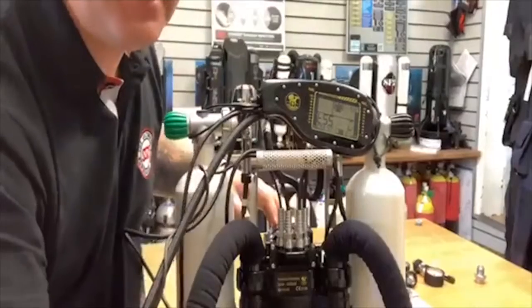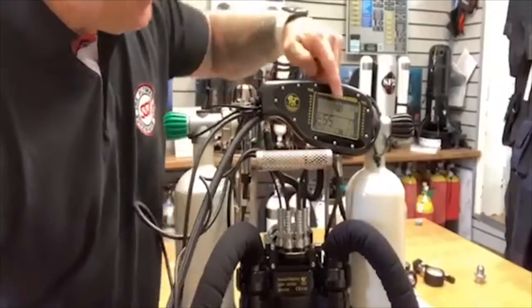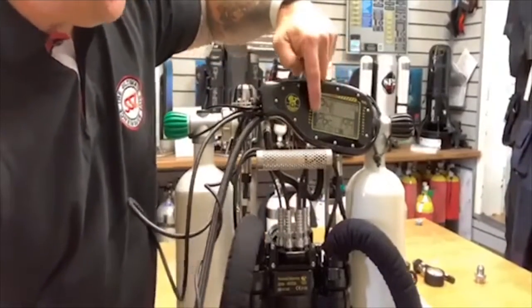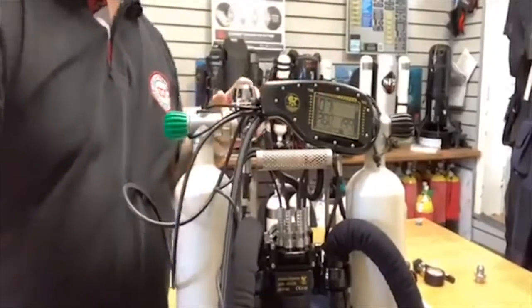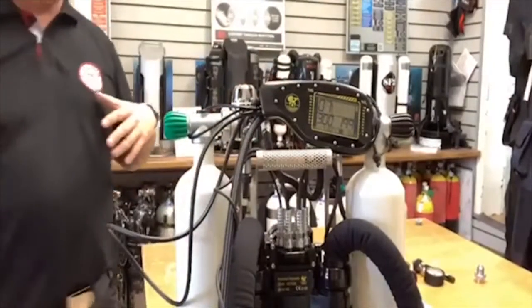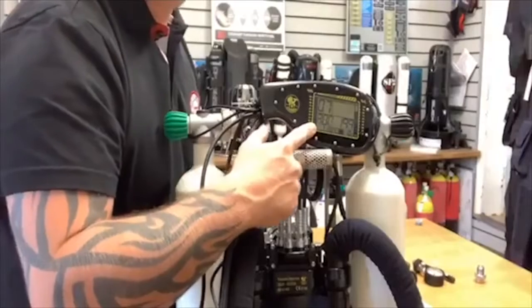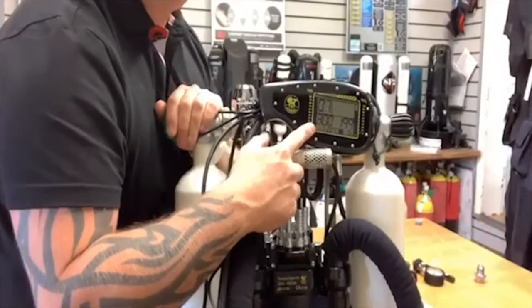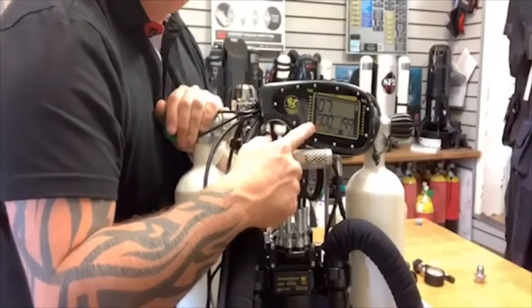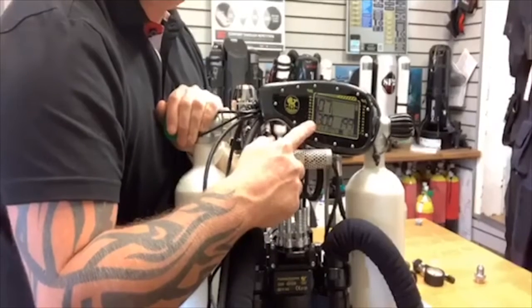that that's working. Test 55 tells me my weeks to service, and test 55 said 105 weeks. So it's got 105 weeks until this machine needs a service again. And it says PBR 300. PBR stands for please do a pre-breathe for 300 seconds. So a 5-minute pre-breathe. It's asking you to do that.